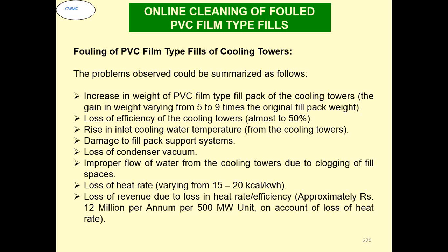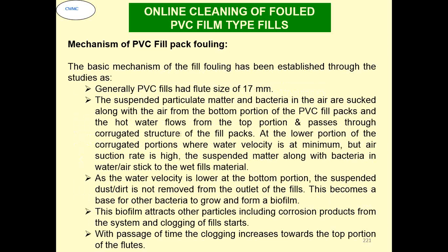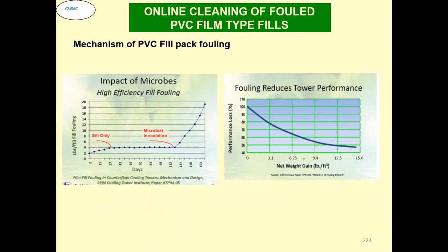There is a gain in weight because of this, and after some time the efficiency of the cooling tower goes down, and because of the weight the entire structure goes down and you can lose a lot. So this is the impact of microbes on the fouling.